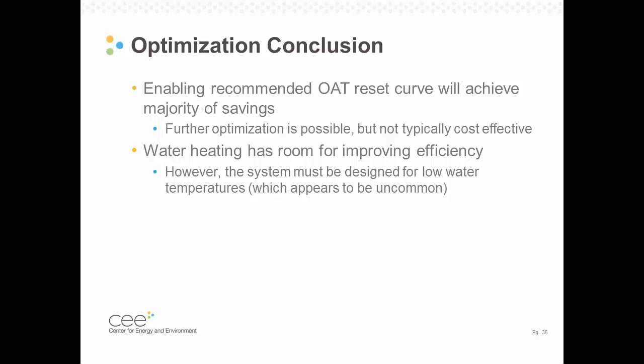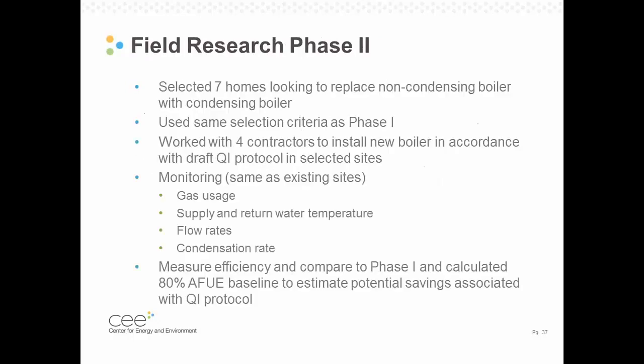So in conclusion on optimization, yes, efficiency improvements are possible, but the condition of the as-found boilers really made it probably not a cost-effective endeavor. And so in our final report, we provide more detailed steps to doing this optimization. But in general, our takeaway from this, and how we developed the quality install guide, is really just to get the boiler set up based on the emitter type and following the manufacturer's install instructions. And that outdoor reset curve, if installed correctly, will really take care of most of the optimization needs in the system.